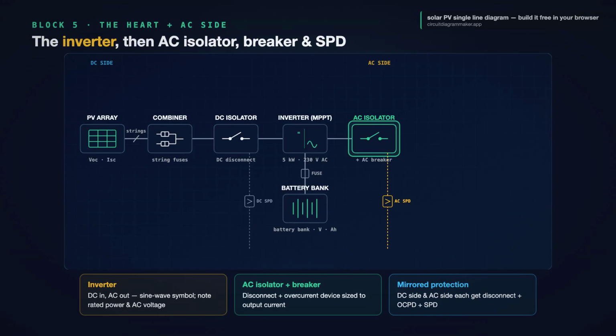On the AC output, the same protection story repeats, mirrored. An AC isolator, a switch to disconnect the inverter from the grid side. An AC overcurrent device, a breaker sized to the inverter's output current. And a second surge protection device, this one on the AC side, again tied to earth. DC side, AC side, each gets its own disconnect, its own overcurrent protection, and its own SPD. Once you see that symmetry, the diagram stops being intimidating.